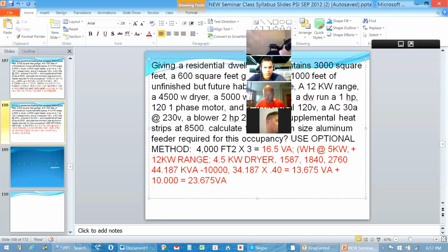So I'm going to take it at 65% of an electric space heating if less than 4 separately controlled units. And that's what we're really looking at there. So I'm going to take 65% of the 8,500 or 100% of the air conditioning under section 1, whichever number is bigger. So I have to look at that 8,500, which is what the heat is, at 65%. It's 5,525. So by the time I take a derate, that heat load's value is less than what the air conditioner is. So I'm going to take the air conditioner load at 30 amps times 230 volts. I'm looking at 6,900 VA for the air conditioning versus the derated heat value.